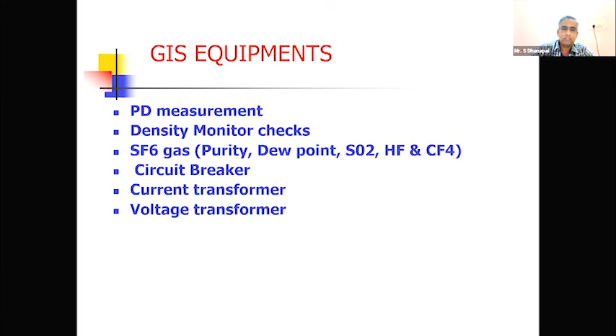As far as GIS is concerned, the only online solution we do is partial discharge measurement. Even there, a lot of other vendors are present, but there is still no clarity on partial discharge measurement and how to analyze the GIS system using it. PowerGrid itself does not have clarity - this is the fact. This has to be made very versatile and easier to monitor. Apart from partial discharge, there should be some other technique to monitor what is happening inside GIS equipment, which is also very important to monitor online. This is a forum where we can say let us introduce a system for online monitoring so that GIS can be efficiently monitored. Thank you so much.